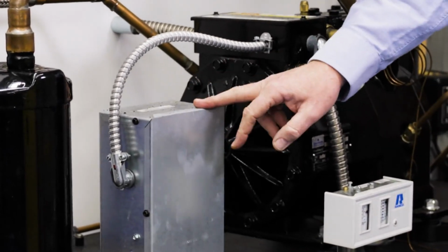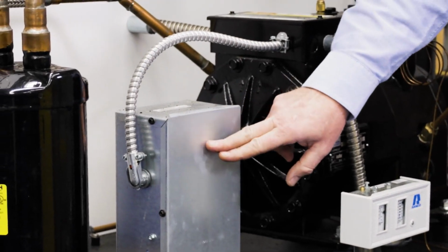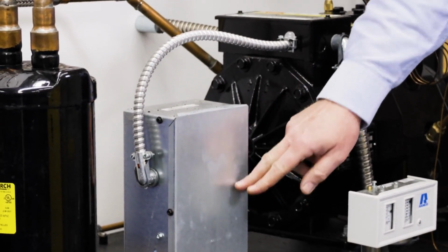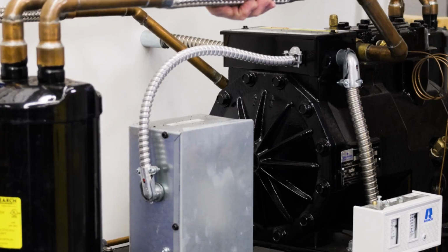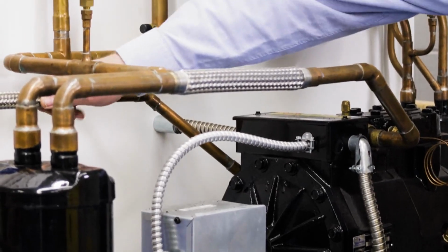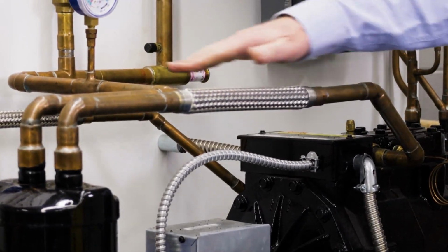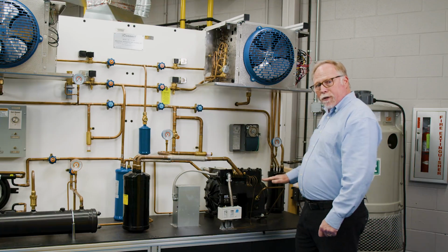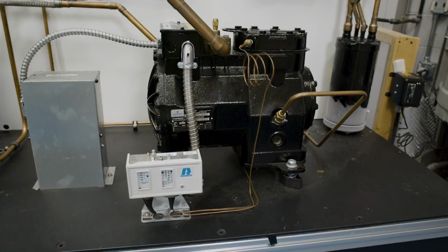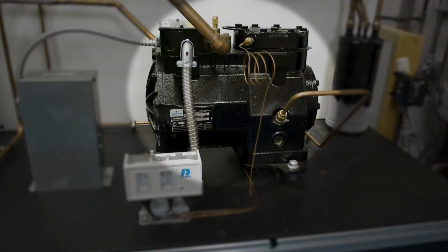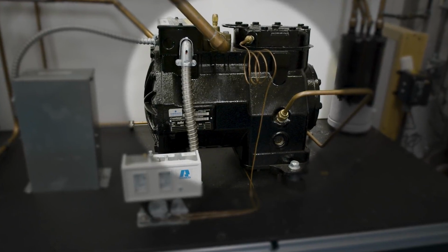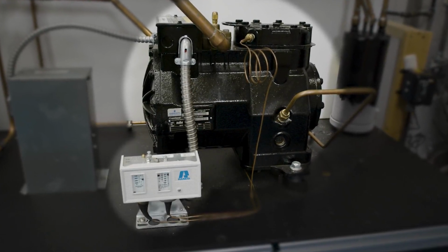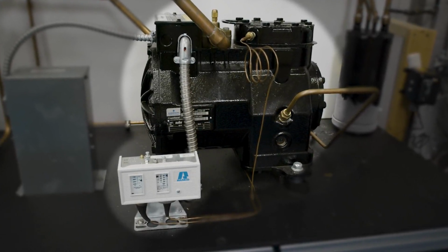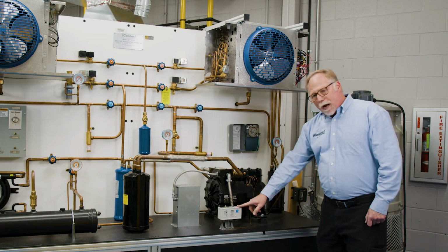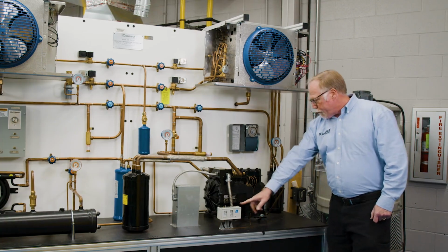Here we have our start kit, which is going to have our start relay and start capacitor. Above it, you'll see here we have our vibration pipes here. And always remember, these need to be in parallel with the shaft of the compressor itself. Then we have our semi-hermetic compressor, our differential pressure switch here for low pressure cut out and cut in, as well as our high pressure cut out.